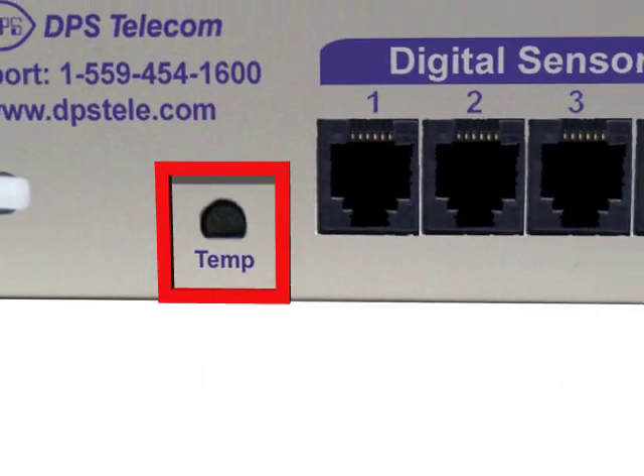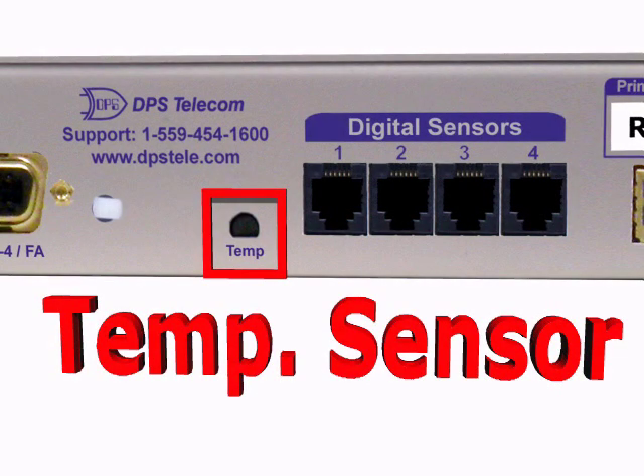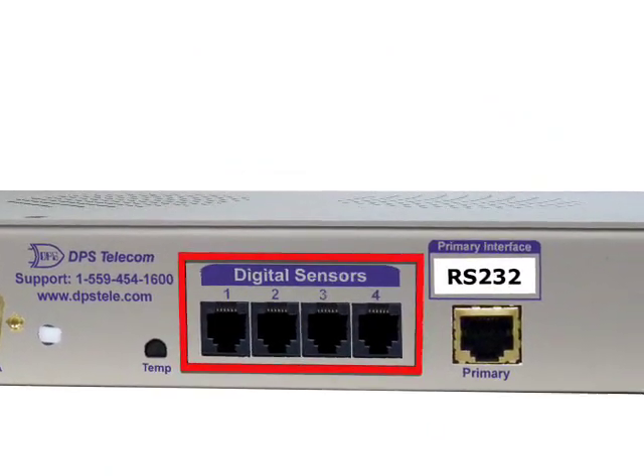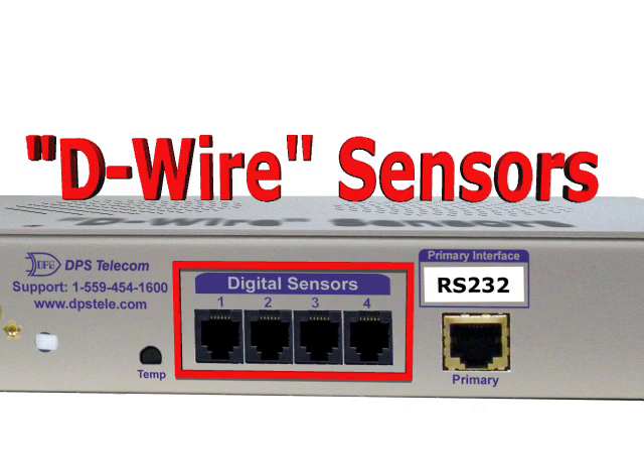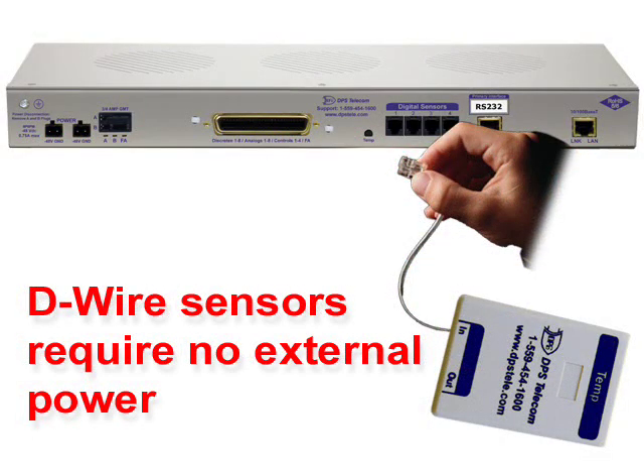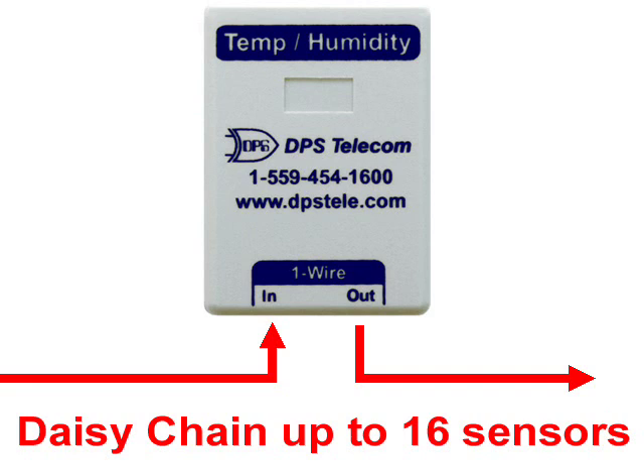Because temperature measurement is so important, the SCADA-Guardian also includes a built-in temperature sensor to give you information about the ambient temperature going on around this RTU. Next to the temperature sensor are 4 D-wire sensor input ports. D-wire is DPS's name for using a single wire to transmit both sensor data and to power your sensors. D-wire sensors can also be daisy-chained from one to the next, giving you more flexibility as you set up your sensors around your RTU. Up to 16 sensors are supported, and you can host all of those 16 sensors off of a single one of the SCADA-Guardian's ports.